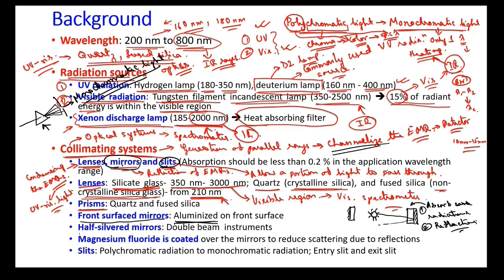There is another type called half-silver mirrors, used in double-beam instruments to split a beam. 50% of the light is allowed to pass through and 50% is reflected to the other side. Magnesium fluoride is coated over the mirrors to reduce scattering due to reflections.